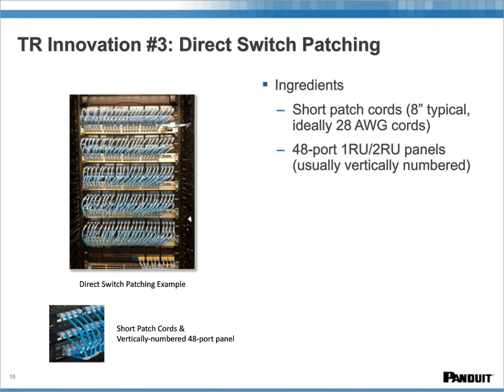But absolutely no question about the individual capability of the cords to carry the power without issue. It simply becomes a matter of the bundle size. And 24 as a bundle size is quite commonly used in the industry anyway.